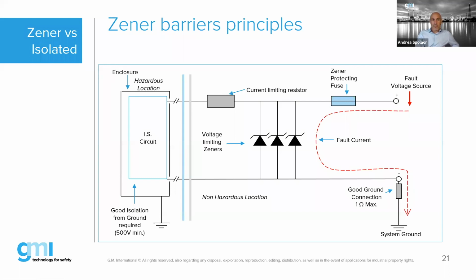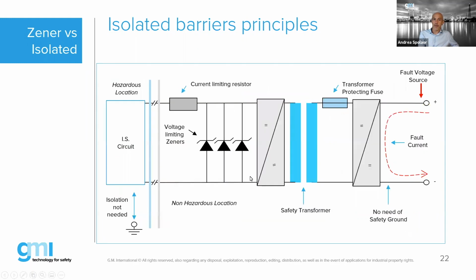The most important things in the application are that the field sensor must have isolation from ground, 500 volt minimum, and the barrier must be connected to ground, 1 ohm maximum. Those are the most important precautions you have to take when you install Zener barriers to protect hazardous area circuitry. In case of fault, the voltage source will be led directly to system ground without interfering with the hazardous area. That is the key point when you realize circuitry with Zener barriers.